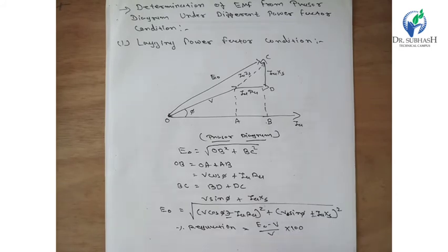This method to find the regulation is very simple, but it does not give an accurate result, because the impedance calculated from the open circuit and short circuit currents is always more than the value at normal voltage condition and saturation.